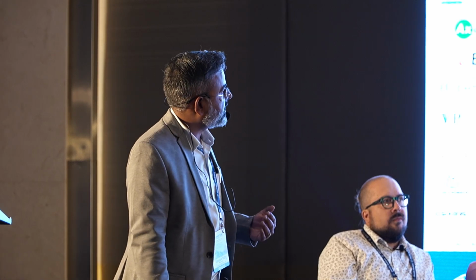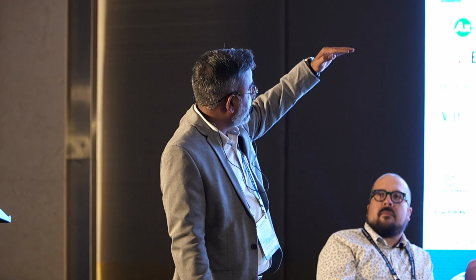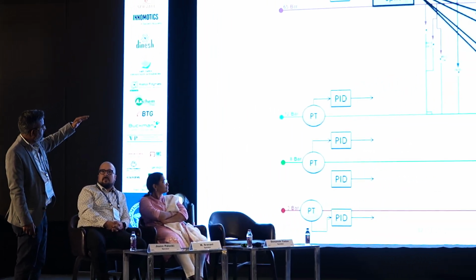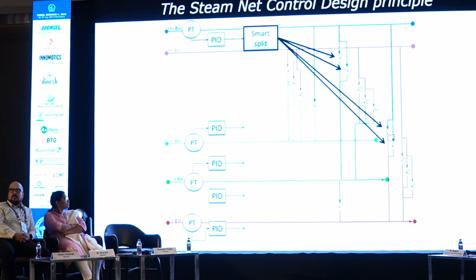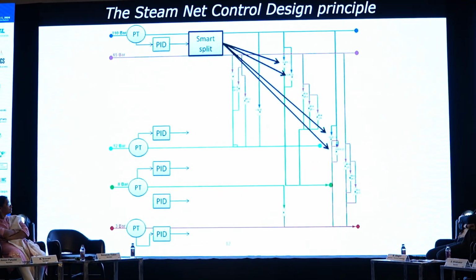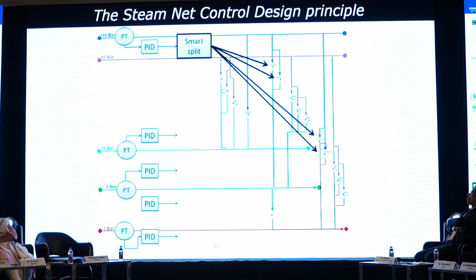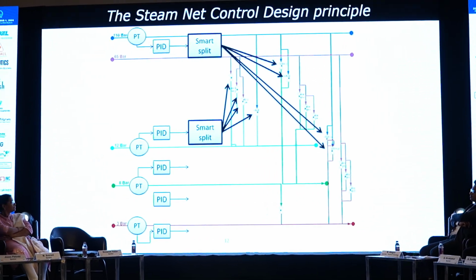We also use a smart split range control strategy, where we have prioritized the control valves' operation in the sense that we reduce the steam venting. We can utilize the steam as much as possible. So the highest priority was given to the highest steam header, which is 110 bar, then 60 bar, 65 bar, and coming down to 3 bar, so that all these valves open in a certain sequential way and steam can be better utilized down to the process, with the maximum being utilized within the process without getting wasted.